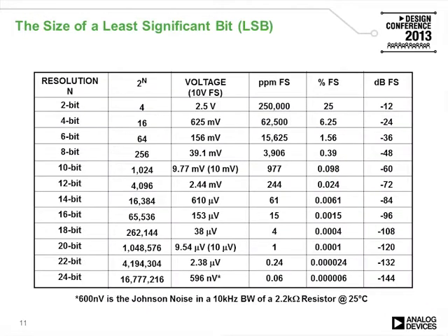What we need to do here is understand what quantization levels we're actually dealing with as we move up in resolution. All things being equal, we'd like to get as much resolution out of our system as we possibly can, because that means the granularity of the input is much more defined, because the step from one digital output to the next is getting smaller and smaller. Quite often we're talking about 12-bit systems kind of as a standard in industrial. We tend to move towards 16 bits, and in some cases we start to get more involved in that, all the way up to 24-bit. But look how the size of the LSB changes over that range.